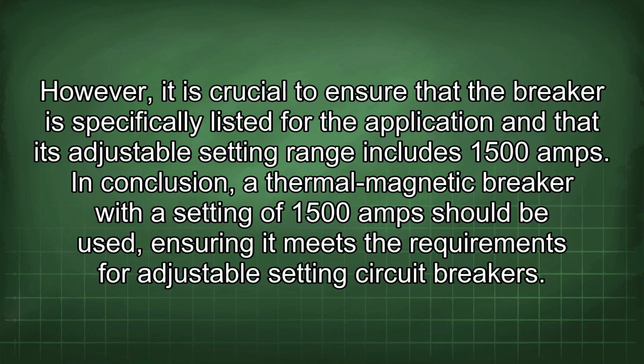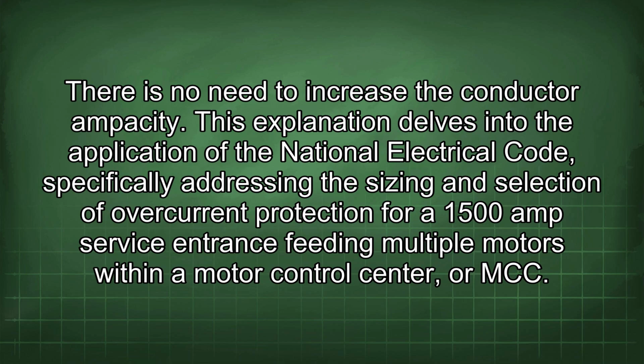However, it is crucial to ensure that the breaker is specifically listed for the application and that its adjustable setting range includes 1500 amps. In conclusion, a thermal magnetic breaker with a setting of 1500 amps should be used, ensuring it meets the requirements for adjustable setting circuit breakers. There is no need to increase the conductor ampacity.